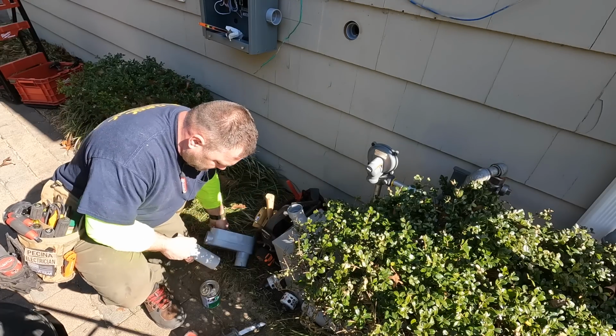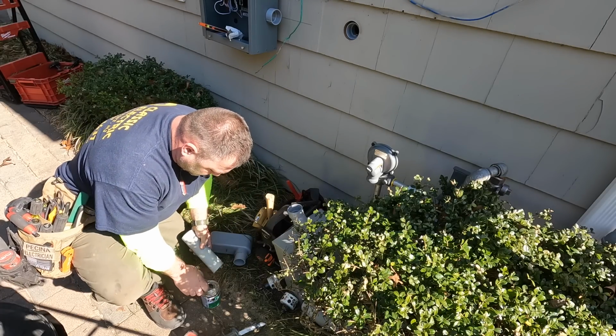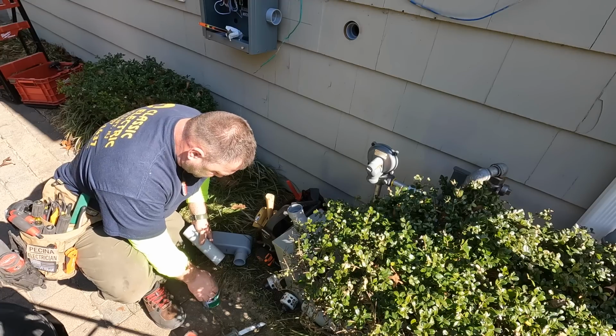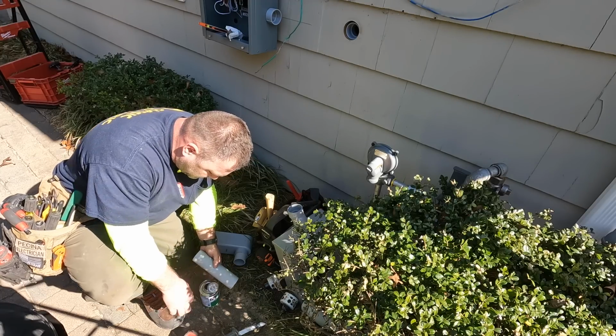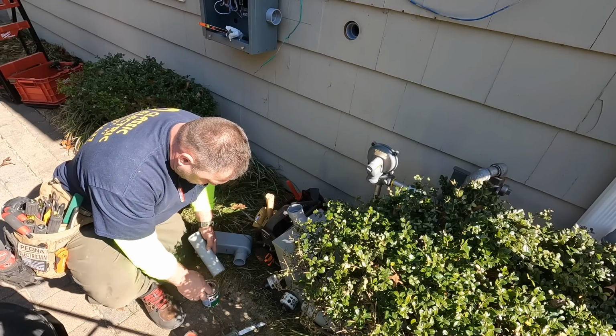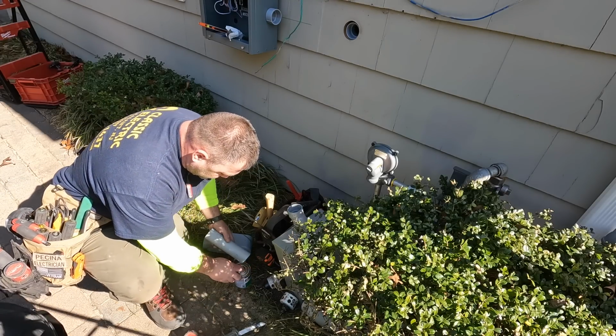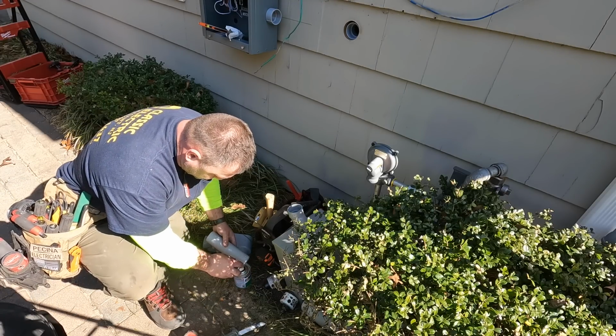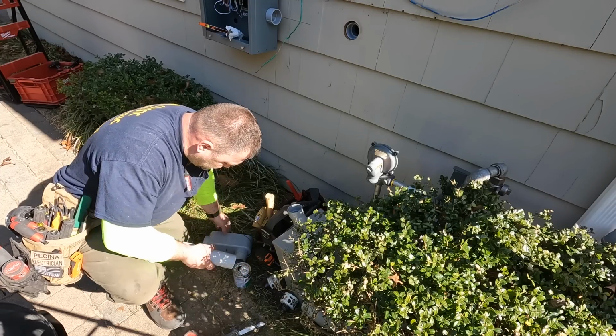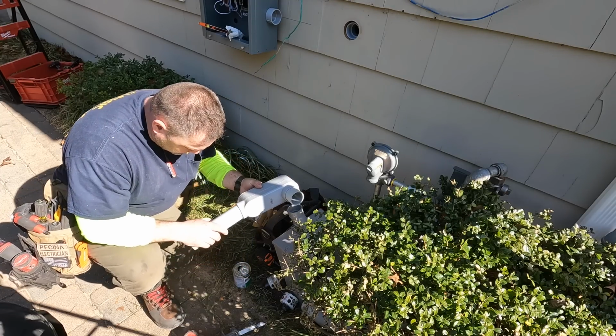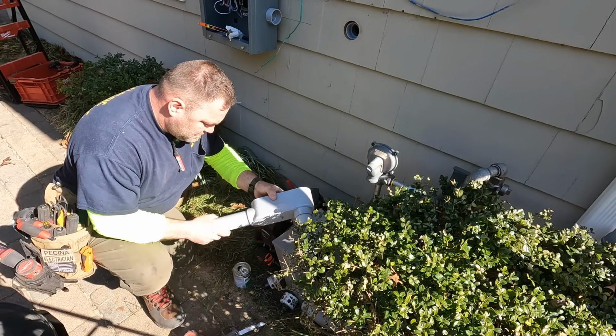Should the conduit enter above those live parts, you'd need to add something known as a Myers hub, which is a little more waterproof. It actually has a gasket on the lock nut itself to deter water from coming in, and then there's a threaded hub at the top, similar to what we use on top of our meters. It's called a Myers hub.